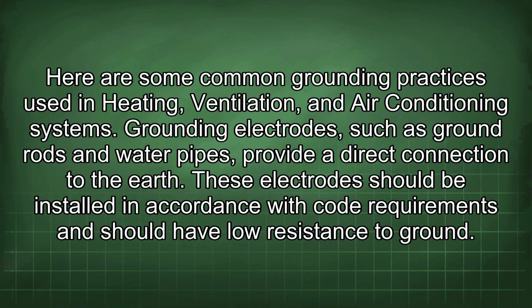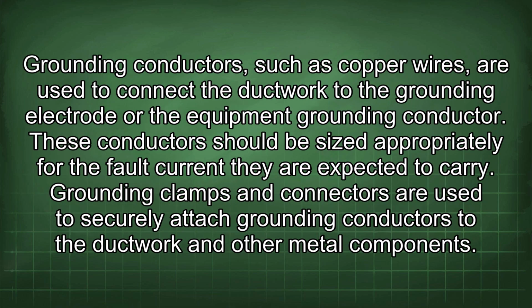These electrodes should be installed in accordance with code requirements and should have low resistance to ground. Grounding conductors, such as copper wires, are used to connect the ductwork to the grounding electrode or the equipment grounding conductor. These conductors should be sized appropriately for the fault current they are expected to carry. Grounding clamps and connectors are used to securely attach grounding conductors to the ductwork and other metal components.